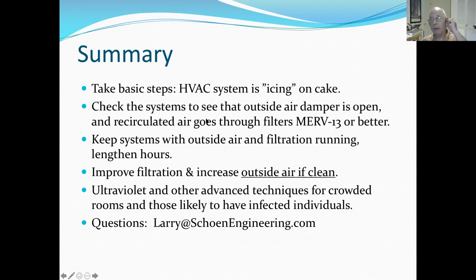Is a break room a good application for a portable air cleaner? Yes. What is the recommended per person CFM? If you go to the manufacturer's website, there's a parameter called CADR, Clean Air Delivery Rate, from AHAM, the Association of Home Appliance Manufacturers. That doesn't mean you can only use it in your home. It's just who rates that particular piece of equipment.